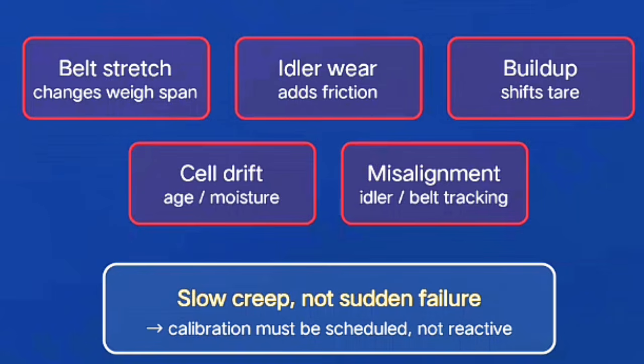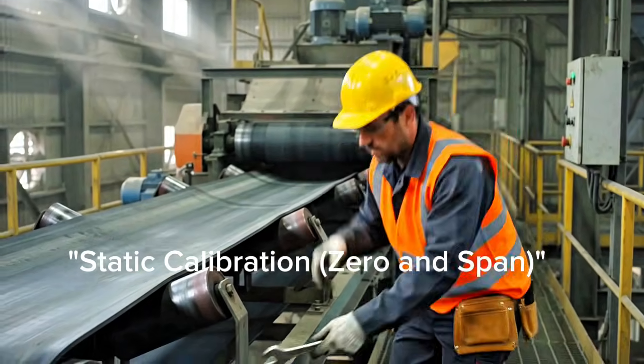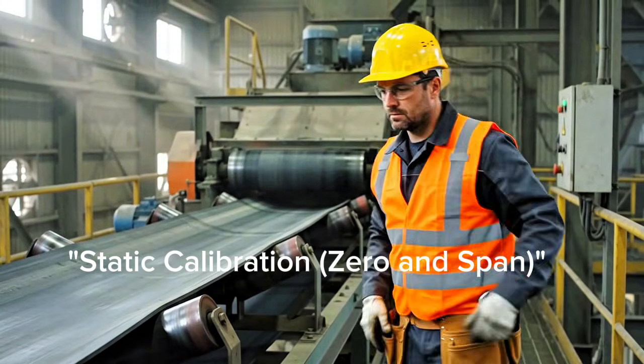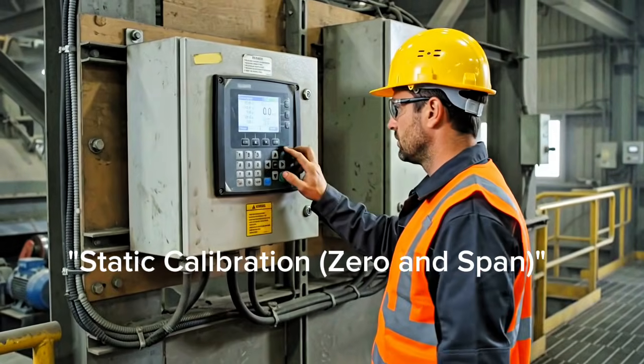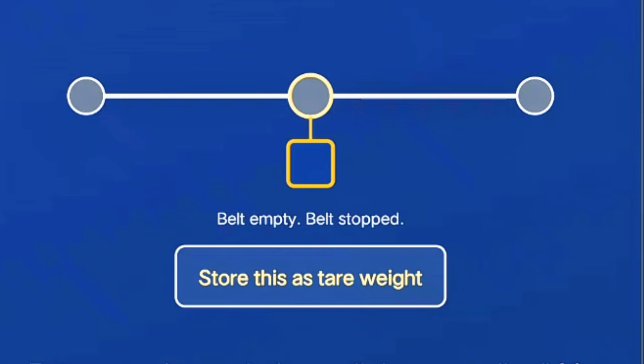None of these are dramatic failures. They're slow creep. That's exactly why calibration has to be scheduled, not reactive. If you wait until dispatch complains or raw mix chemistry drifts, you've already been running wrong for weeks. Static calibration is the first step, done with the belt stopped. It has two parts, zero and span.